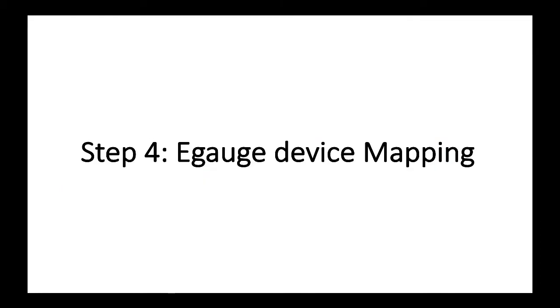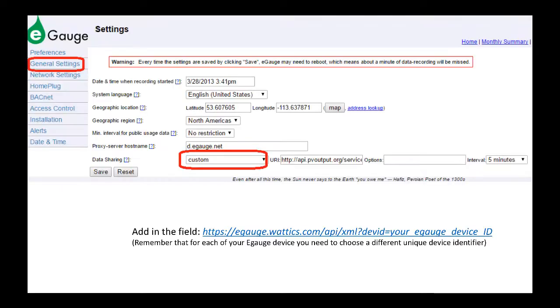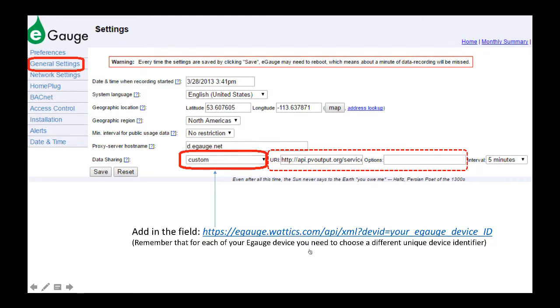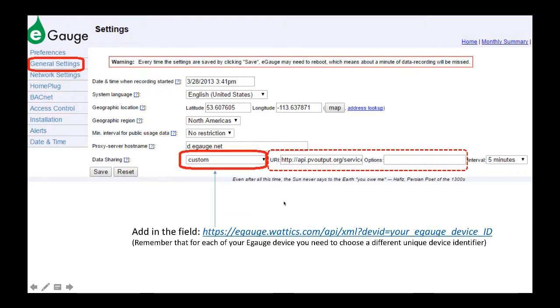So step number four, we go back to the eGauge device mapping, and at this point, we go to General Settings, Custom, and here we have to put the HTTPS URL link, which is the egauge.wattics.com link, where the data has to be pushed to. So once we put the URL, and then we save this page, their device, the eGauge device will start pushing the data regularly to the Wattics interface.